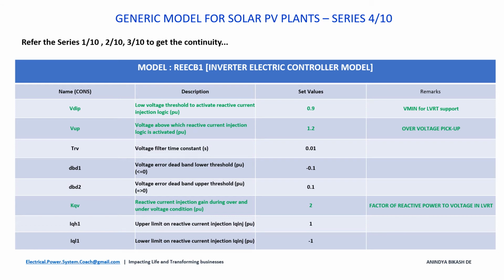And if there is any shortfall, in that case, you have a choice to set the KQV values. It can be varied from 0 to 4 and you can adjust this value. So in one particular project, we had to set this KQV value more than 2 and we had to set it approximately 2.5, and that is a very practical scenario based on the system condition.